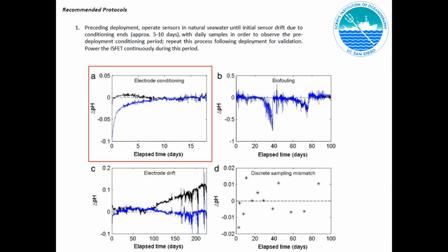And the one thing I'd like to point out that does get a little bit technical is that there are two different lines here with completely different conditioning periods. If you look at the black line, this is the Durafet signal based on its internal reference electrode, and the blue line is the Durafet signal using this external reference sensor that we integrate into the SeaFET and SeapHOx. Clearly the blue line has a much longer conditioning period, and the black line has a very short, rapid conditioning period that's associated with the liquid junction of the internal reference conditioning to seawater.